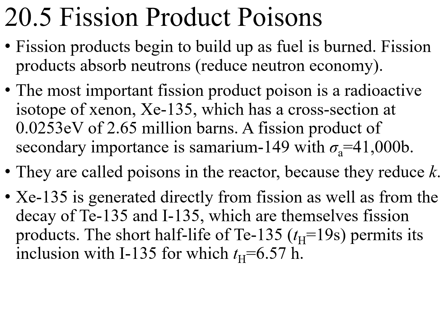In that case, if the reactor is shut down, you cannot restart the reactor quickly because you have a large quantity of this fission product poison inside the core. If you want to restart the reactor quickly, you have to withdraw lots of control rod and make this reactor very unstable. The normal way is that you wait a couple of days until this xenon-135 decays out, then you can restart your reactor.